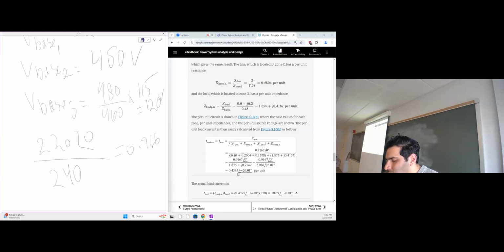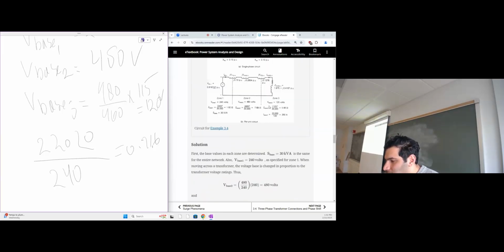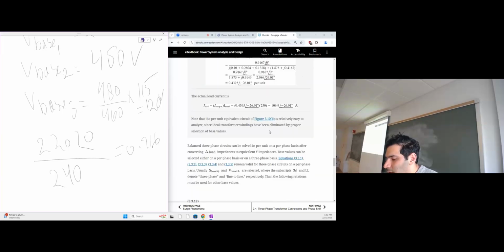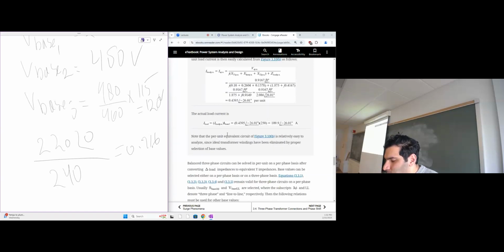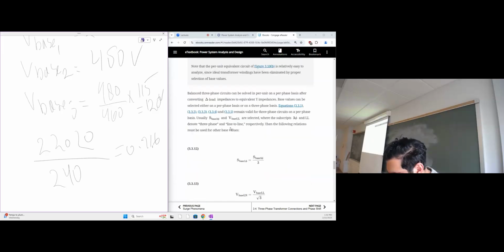If I'd like to know the real value, which is circulating here, I have to multiply by the I base 3, which is 250. So I multiply the resulting per unit value by 250. It came out to be 109.9 something amperes. So this is how we normally do things, and per unit values really help a lot in understanding the system on a unified base.